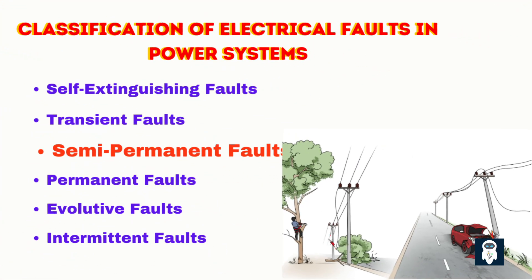Semi-permanent faults require protective devices to operate and may need one or two resets by automatic recovery mechanisms. These faults arise from conditions that are more persistent but still self-limiting over time, caused by external factors that degrade or clear with time, and are typically resolved without manual intervention after multiple resets. An example is vegetation growth — branches brushing against power lines and burning off during fault currents — resulting in temporary outages and brief interruptions from multiple resets.